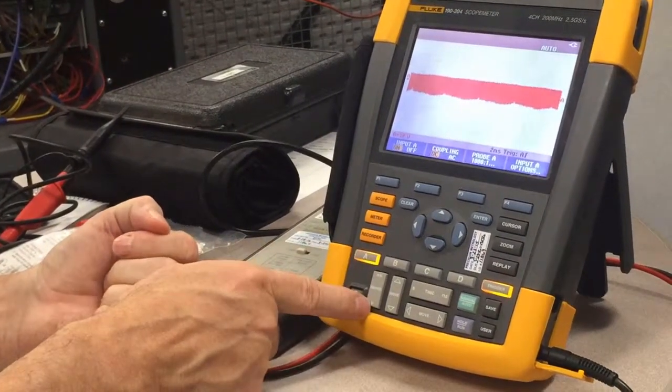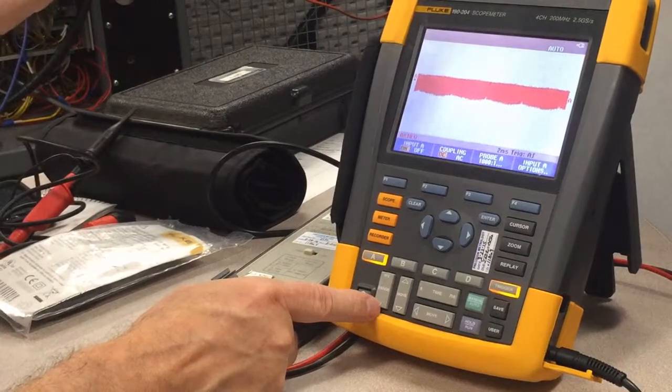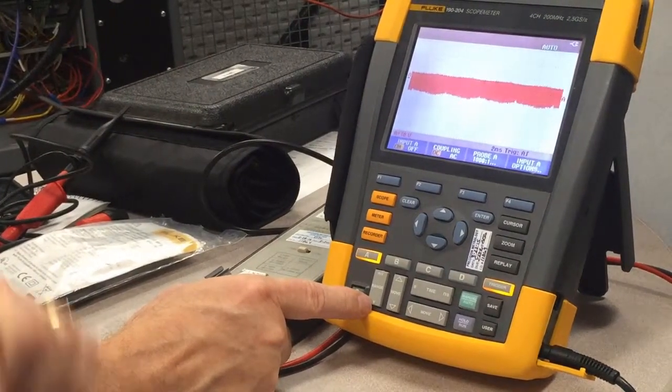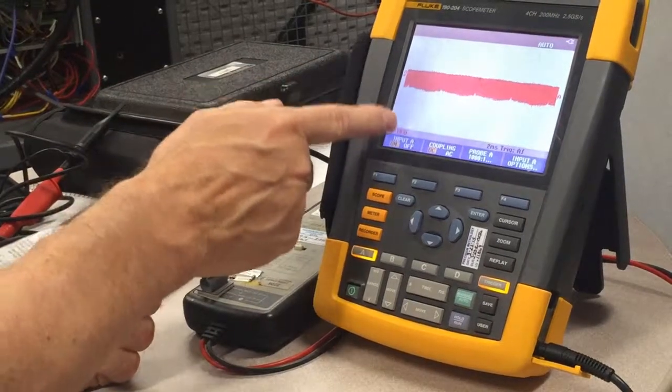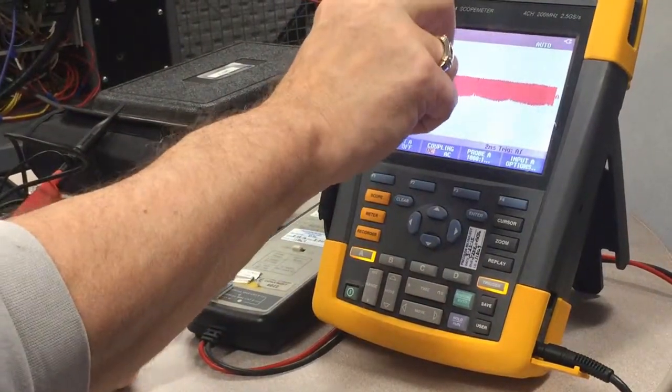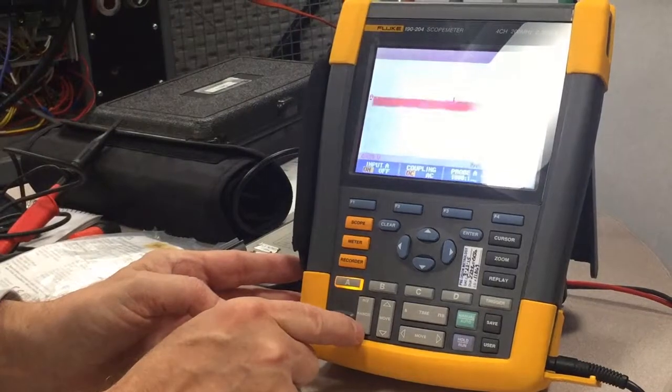Okay, now make sure that the input is on, your coupling is AC, your attenuation is 1,000 to 1. And the next thing we're going to do is we're going to set the vertical scaling, the volts per division. In this test of reflective wave measurement, we know approximately that the peak voltage is going to be well over 1,000 volts. So our volts per division has to be set so when we get the waveform, it doesn't go off the screen. So we're going to increase the voltage per division. Right now it's set for 10. We're going to increase it to 500 volts per division.